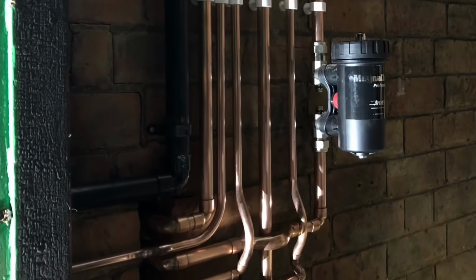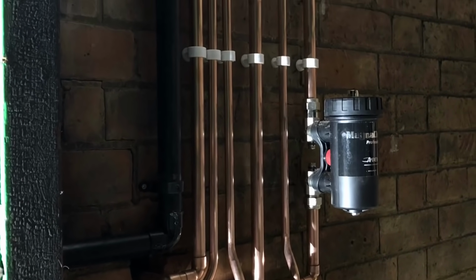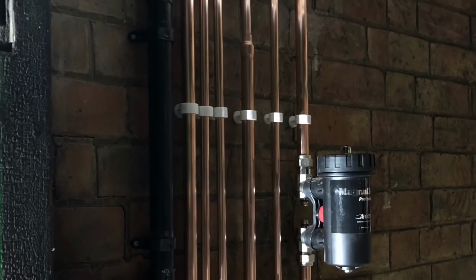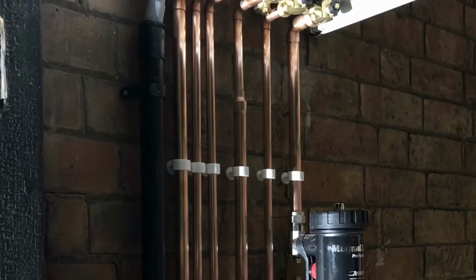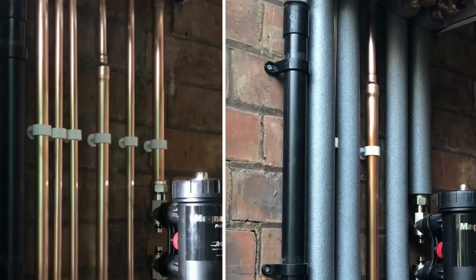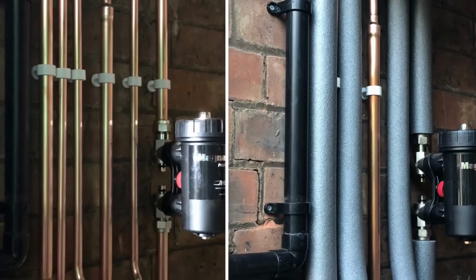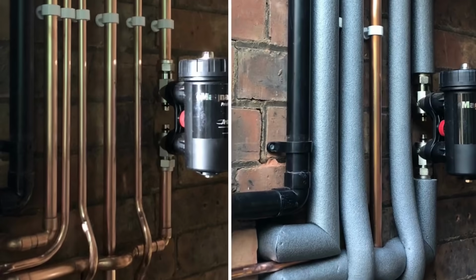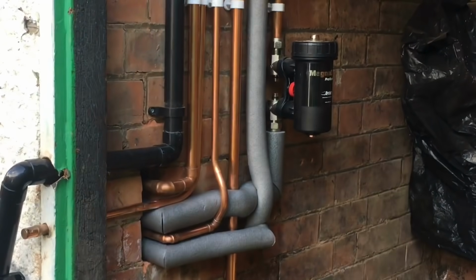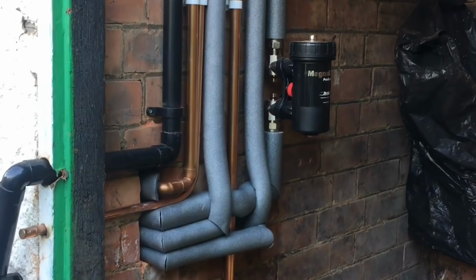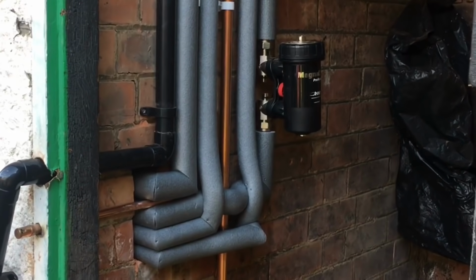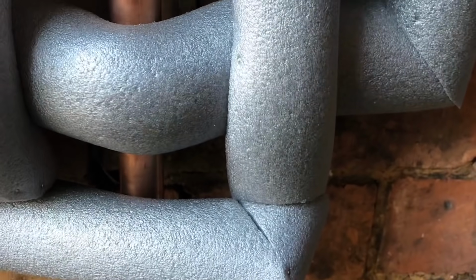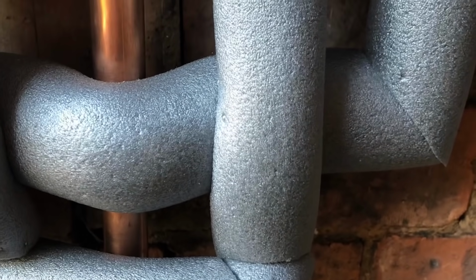So I did end up replacing this boiler, and unfortunately, because I was so busy, the phone wouldn't stop ringing, I didn't actually get around to filming this install. Tried to make a decent job of the pipes. Someone did point out to my Instagram though that the gas pipe, I probably should have bent that over the return and the cold. It would have been a better job, but you live and learn. Also, it was quite tight to get the lagging on, but I did my best with that as well. So apologies for not filming the install.